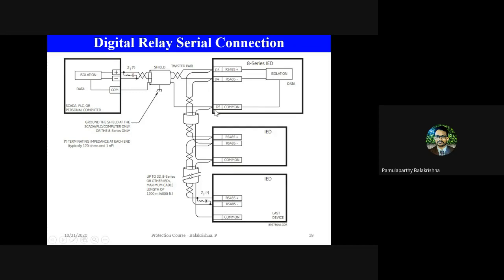So it has to come here, it has to go here, it has to come here, and it has to go here, okay? Only the intended relay that is supposed to take the message will take that message, and further it will not send to the downstream devices. Okay, so you will have disadvantages and delays in communication when you have serial based communications.